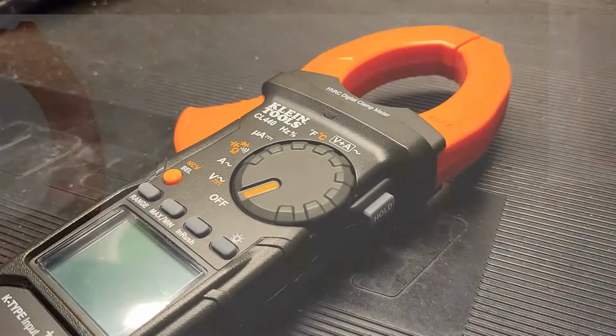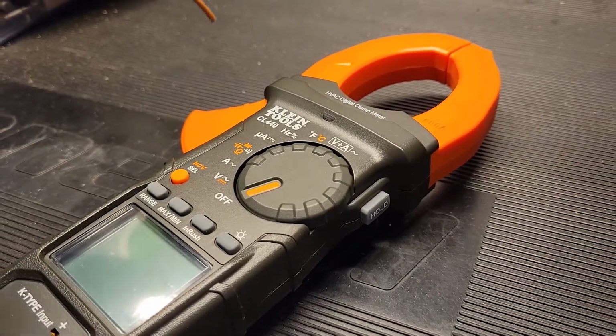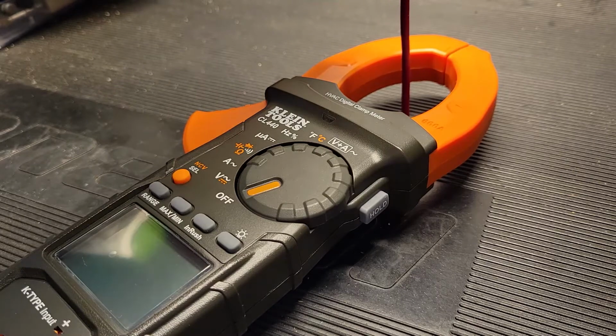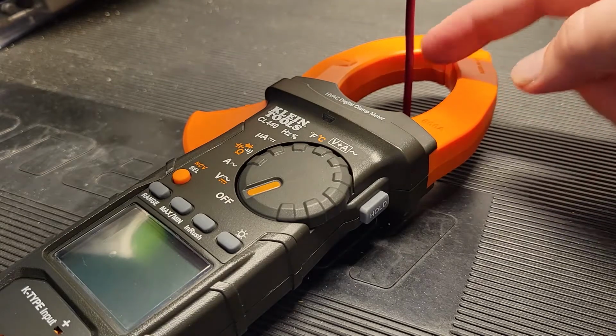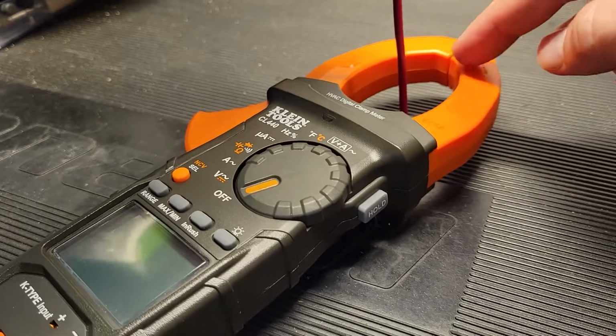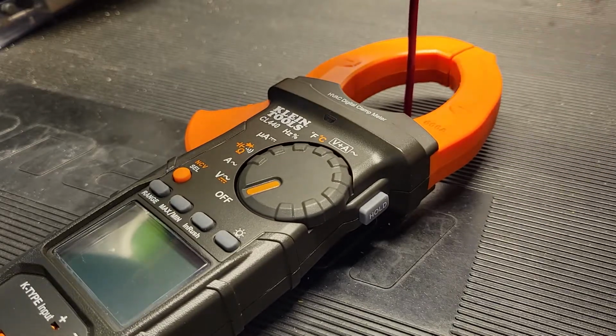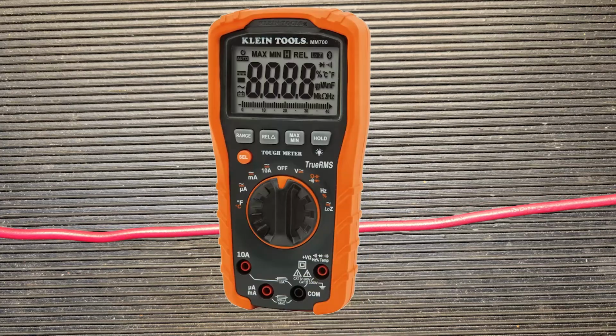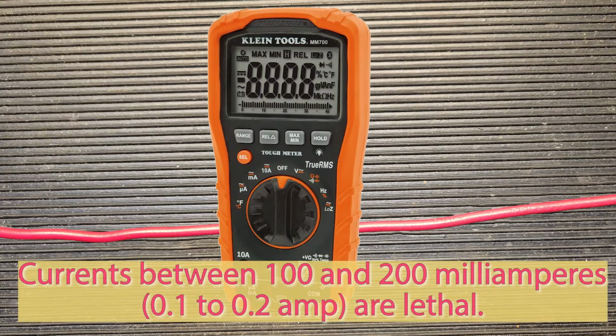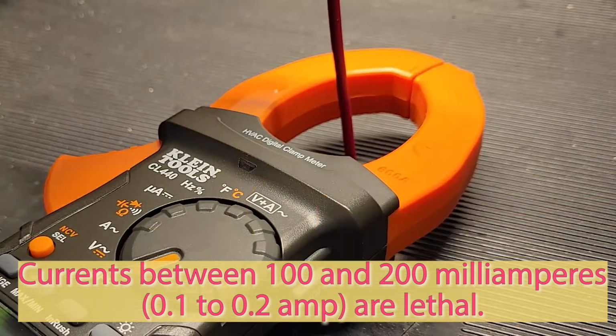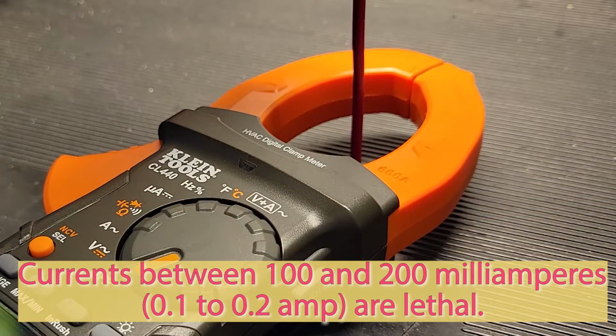So why a clamp meter? The thing the clamp meter brings to the game is that all you have to do is insert a live wire inside the clamp area, and it will read the current of that wire without physically having to cut and put the tool in series with it, which is what you'd have to do with a multimeter, which is why multimeters usually can't go beyond 10 amps. When you stop to realize that at less than an amp you can be killed, there's a good reason for getting your amp reading without physical contact.